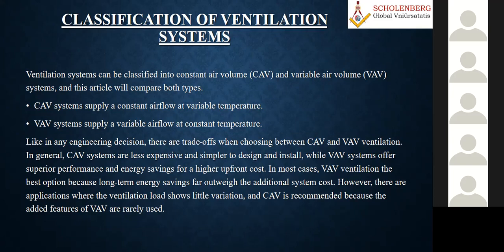One is called the constant air volume system, which was a very old system. We used it the majority of the time earlier, maybe 25 or 30 years ago. A simple system: we calculate this much dehumidified air, and then based on that we design the velocity. There will be a common duct, a common plenum. We have branch ducts, and we know the load calculation. On that basis, for every room, based on the load, we determine how much CFM is required. We take the grill velocity, and then the branch ducts.